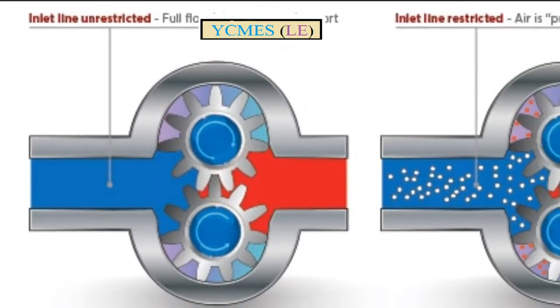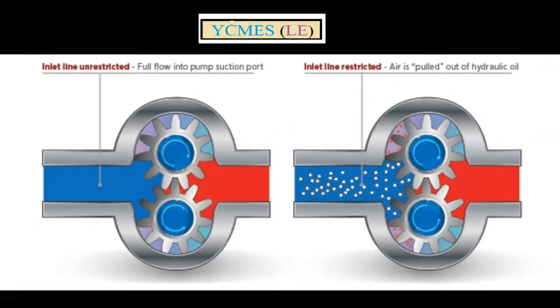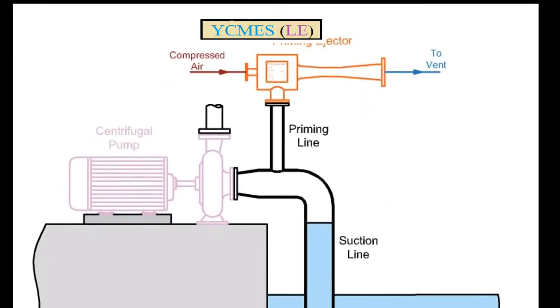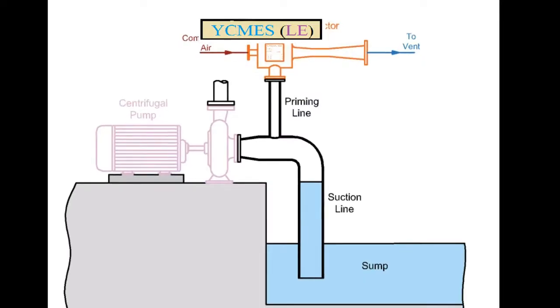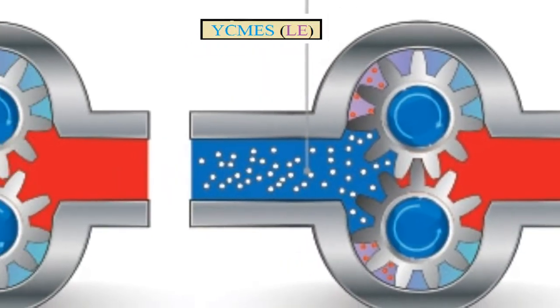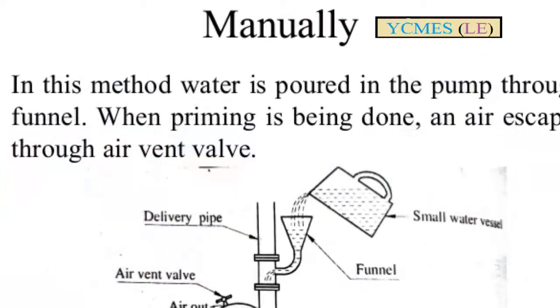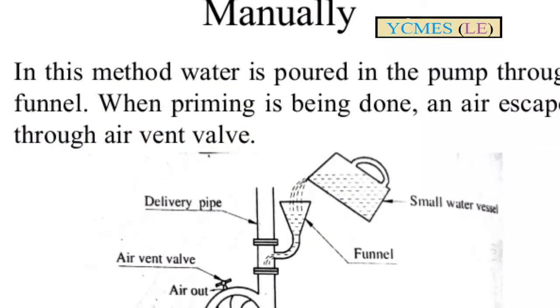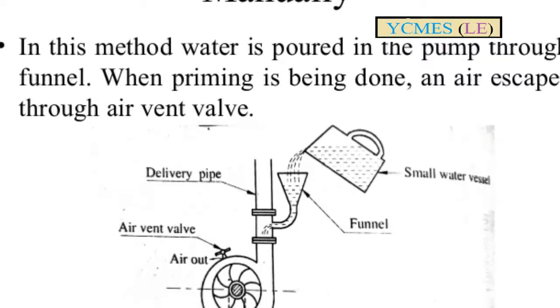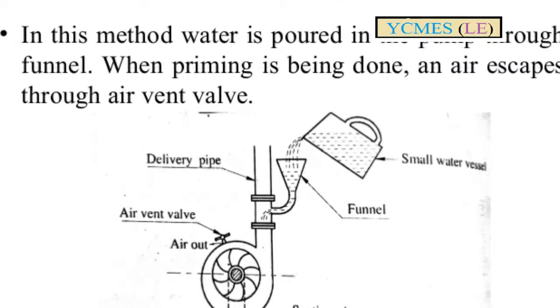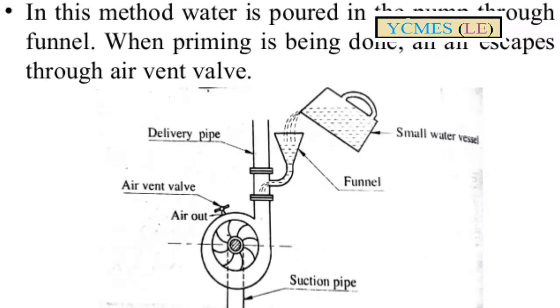As for modern pumps, they have a priming attachment built in. But for older pumps, priming is very important and must be done manually. The priming process involves filling the casing line and suction line with water.